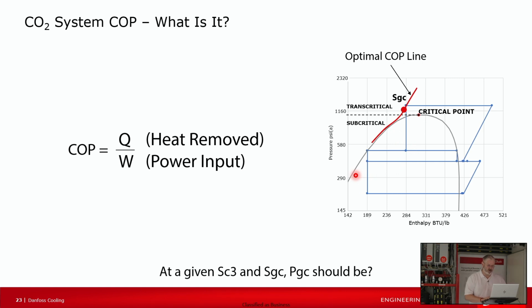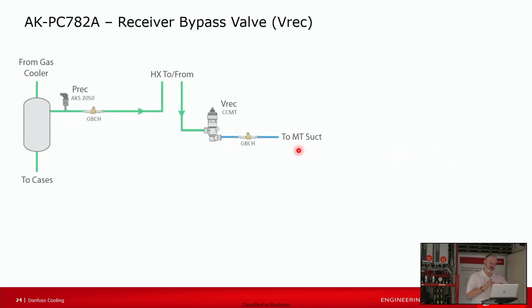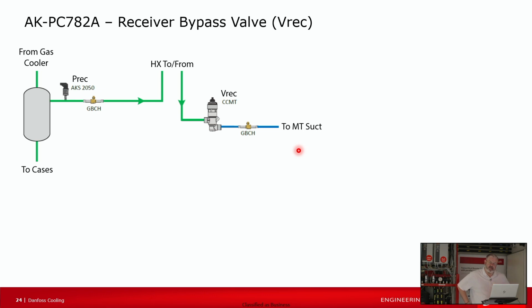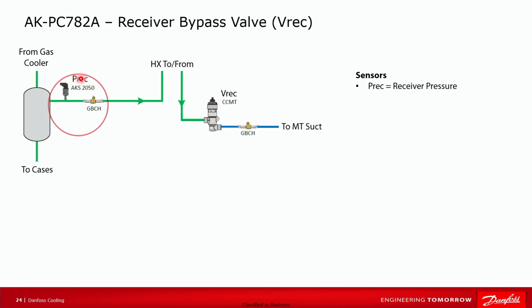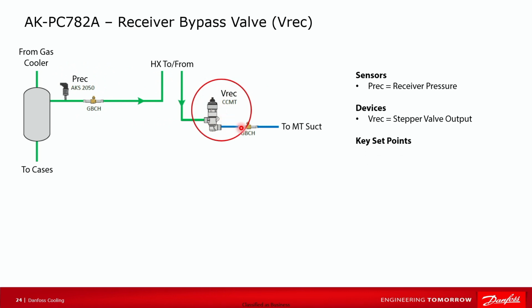And then the last one on the control, the fourth area that we highlighted, is the receiver bypass valve. It's very simple. It's looking at the pressure in the top of the receiver and using the receiver valve to open and close. As the pressure rises in the flash tank or the receiver, this valve opens to relieve some of it. As the pressure drops, it closes off to back some pressure up and raise it back up. For the key set points, you tell it what set point you want. We use 560 or 520 for our example, and then you give it a minimum and a maximum.